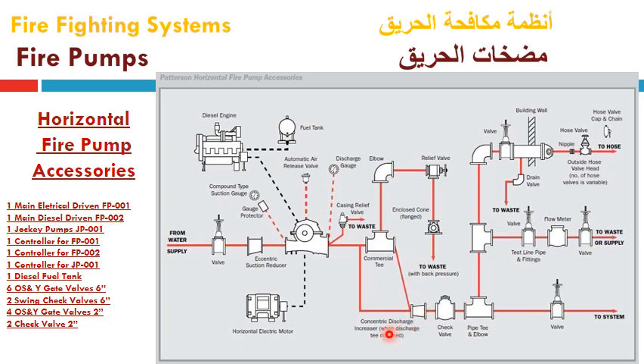When discharge T is not used, we can use this concentric increaser just downstream of the discharge flange of the pump to adapt between the discharge flange diameter and the discharge line diameter. Then we will use the UL and FM approved check valve and go to the system after using another isolation valve, such as an OS&Y gate valve, which will be located here on this discharge line.